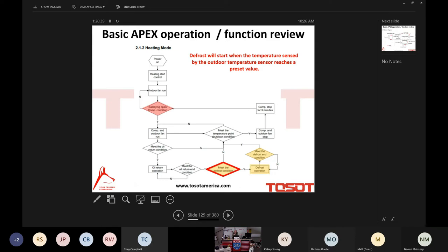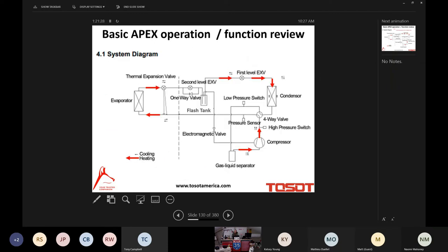Something I just want to point out in the heating mode is if it were to go into defrost, and the defrost will start, guys, when the temperature sensed by the outdoor temperature sensor reaches a preset value. So if it were to go into defrost, it just goes through that process. And your customer actually has some control over the defrost cycle. They can force it into defrost. I'll show you how to do that. But also they can elongate the defrost cycle. Something unique about the Apex outdoor unit is one of the dip switches allows you to go from the standard defrost cycle to what they call a strong cycle, which simply means it elongates the defrost cycle if additional defrosting is required. And again, I'll get to that hopefully after break.